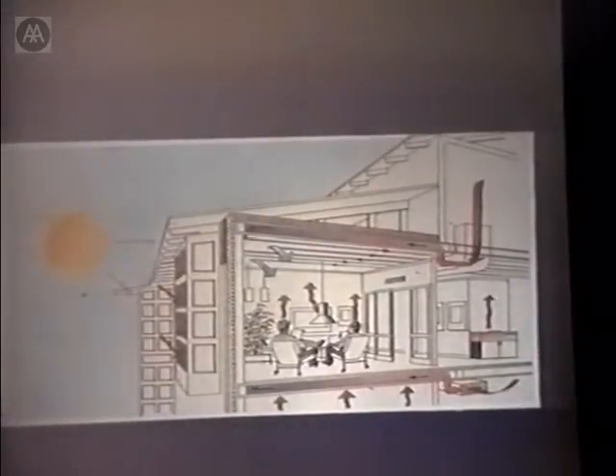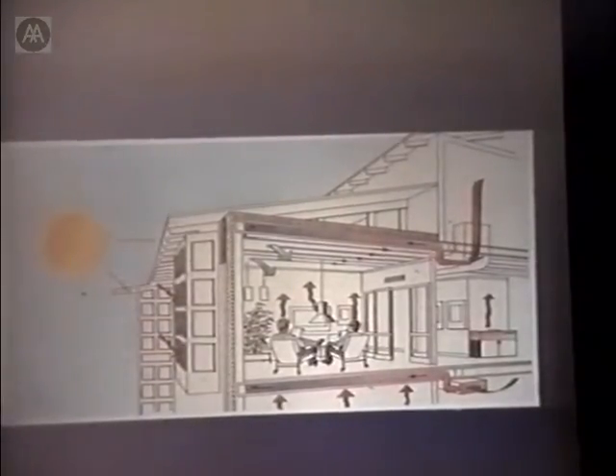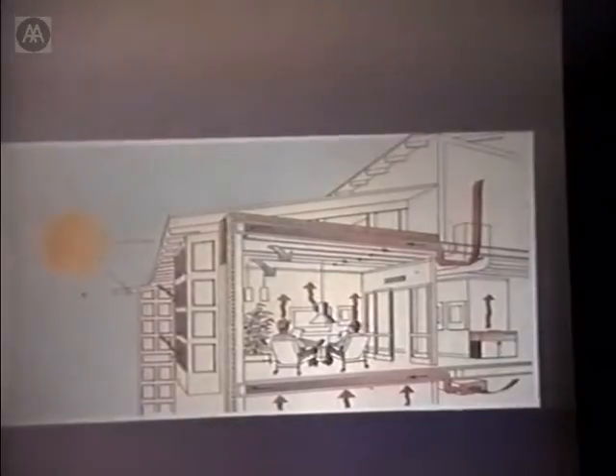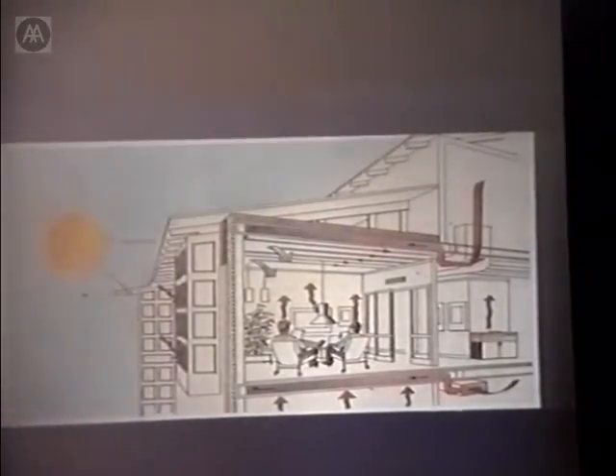During the day, ventilation continues at a high rate. You've got heat being radiated down from the slabs, or radiated back up if it's cool, and the air goes through the slabs, cools itself down, and blows into the room. So you've got two things happening: heat being removed by the air, and heat being moved by radiation to the concrete slabs.